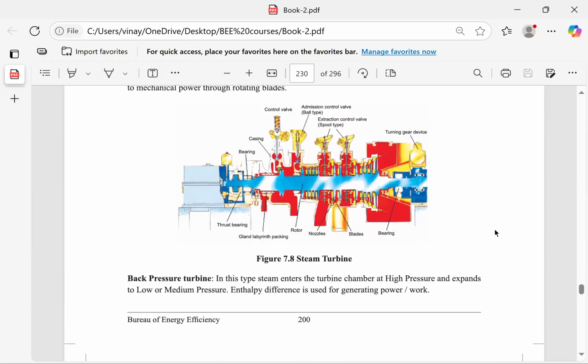The turbine referred here gives you the idea only so far as the extraction and condensing turbines are given. The turbine control valve controls the entry of high pressure, high temperature steam into this chamber all around. This high pressure, high temperature steam forces its way, expanding as it goes, and passes through fixed and moving blades.